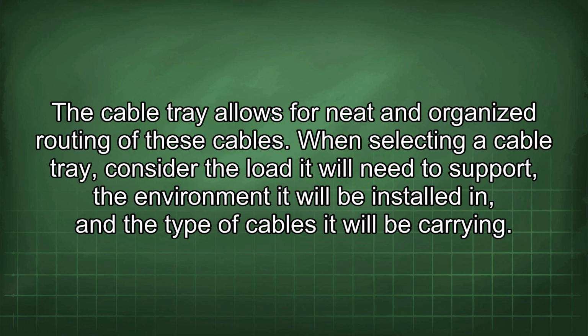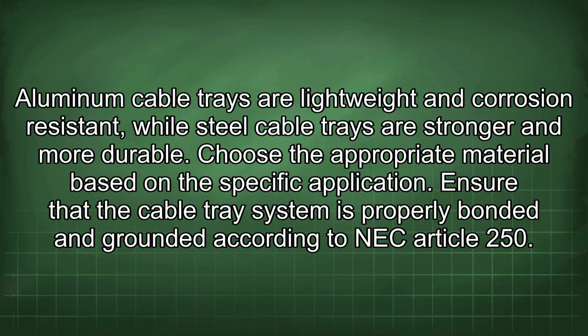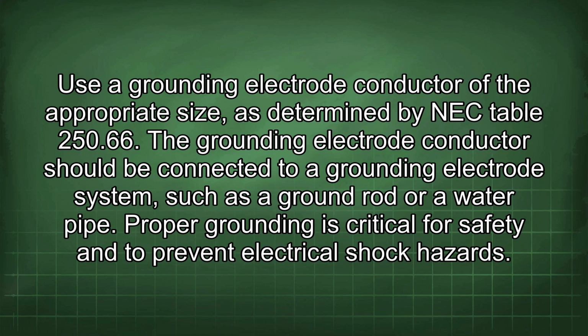When selecting a cable tray, consider the load it will need to support, the environment it will be installed in, and the type of cables it will be carrying. Aluminum cable trays are lightweight and corrosion resistant, while steel cable trays are stronger and more durable. Choose the appropriate material based on the specific application. Ensure that the cable tray system is properly bonded and grounded according to NEC Article 250. Use a grounding electrode conductor of the appropriate size, as determined by NEC Table 250.66. The grounding electrode conductor should be connected to a grounding electrode system, such as a ground rod or water pipe. Proper grounding is critical for safety and to prevent electrical shock hazards.